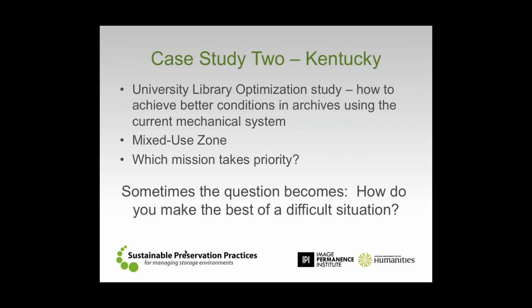This one just very quickly because it's important. You run into a lot of zones out there where you have a mixed use zone and you're trying to figure out with a mechanical system, how do I manage a preservation environment that is in one room off of this air handler, and the same air handler is trying to control, in this particular case, a technical services division for a university library. All people, no collections, no preservation goal at all. So on one floor, that mechanical system is trying to achieve 60 degrees and a moderate relative humidity, and on the floor above it, it's trying to maintain 70 degrees.